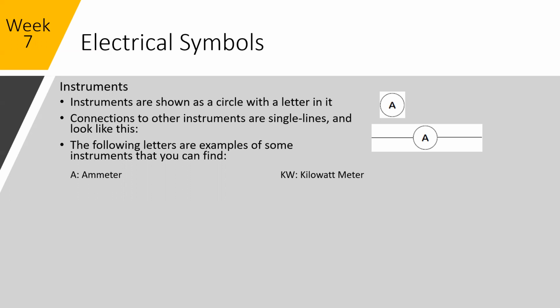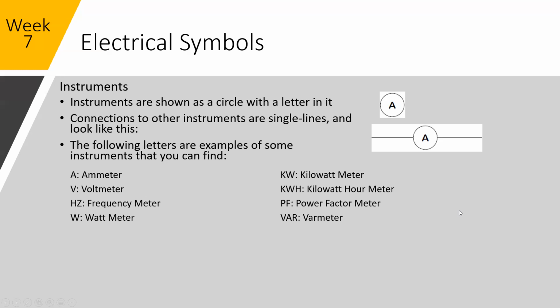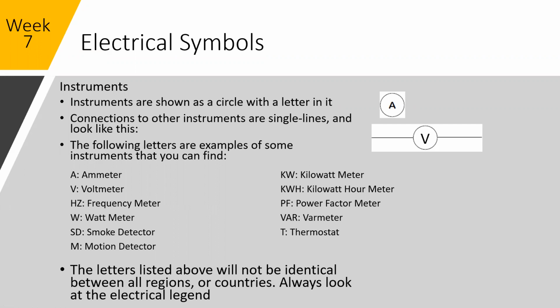There's going to be a legend in there that will tell you what the different symbols mean for that specific project. So, for example, you could have an A for an amp meter, kW for a kilowatt meter, V for volts, HZ for frequency, which would be the speed of drives, PF power factor, and there could be many more. As you run out of characters, the more devices that you have, there's only so many 2-letter character combinations you can get. So you'll see some that'll have numbers. Depending on the drawing that you have, you just have to pay attention to what they are meaning. So again, the letters listed above will not be identical between all regions or countries. Always look at the legends for the drawings that you have.